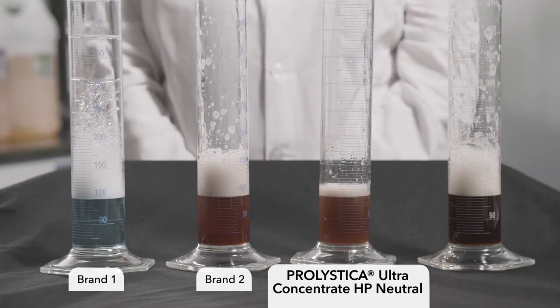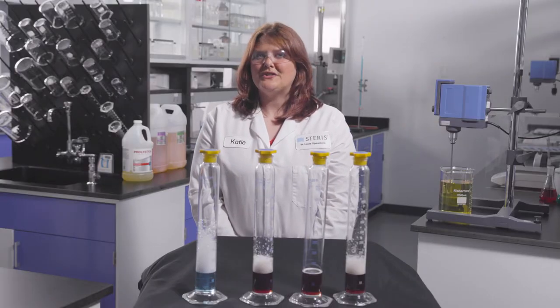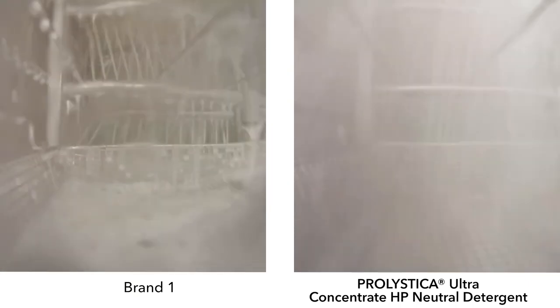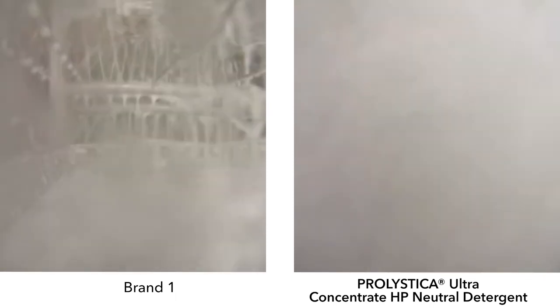The difference is clear for manual cleaning, but let's take a look at how Prolystica compares to other detergents in the washer. Less than two minutes into a washing phase, brand one, a well-known chemistry, shows an increased level of foam. As the level of foam increases, the speed of the spray arm decreases as a direct result of excessive foaming. The slowing of the washer arm reduces the impingement, decreasing the cleaning capability of the washer.